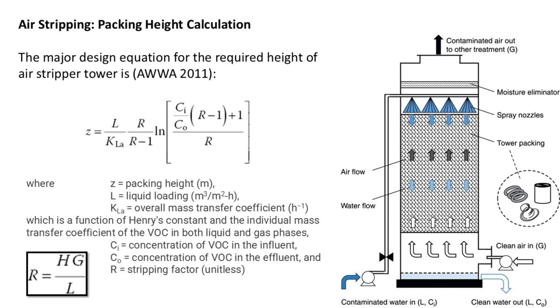Finally, let's look at one example for its design calculation. The major design equation for the required height of an air stripper tower is recommended in the AWWA design book. In this equation, Z is the packing height, L is the liquid loading, and KLA refers to the overall mass transfer coefficient, which is a function of Henry's constant and the individual mass transfer coefficients of the VOC in both liquid and gas phases. The influent and effluent concentrations of VOCs are also decisive. The R in the equation is called the stripping factor, a crucial parameter for determining the ability of an air stripper to remove a specific contaminant. The stripping factor R is affected by both the liquid-gas loading and the Henry's Law constant.